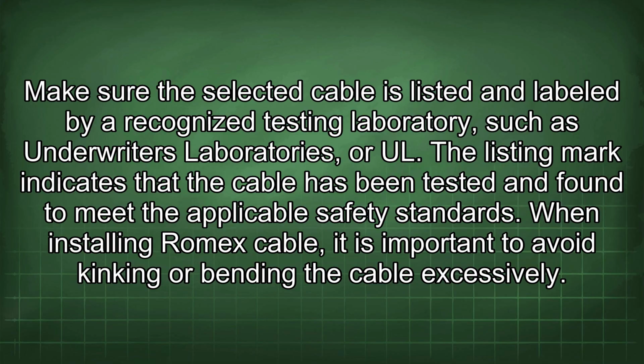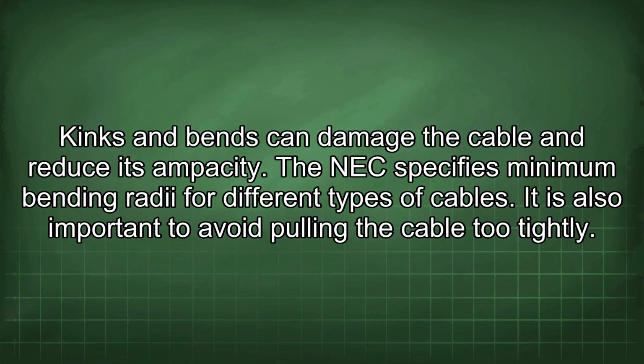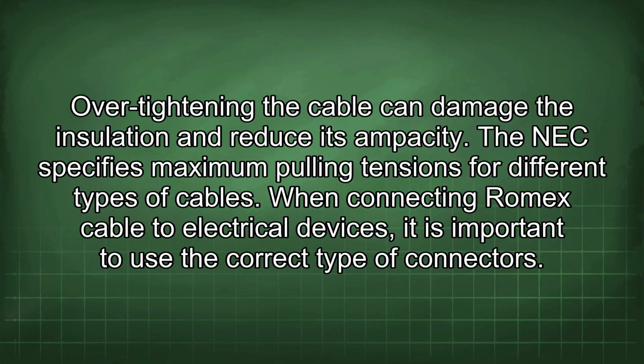When installing Romex cable, it is important to avoid kinking or bending the cable excessively. Kinks and bends can damage the cable and reduce its ampacity. The NEC specifies minimum bending radii for different types of cables. It is also important to avoid pulling the cable too tightly. Over-tightening the cable can damage the insulation and reduce its ampacity. The NEC specifies maximum pulling tensions for different types of cables.